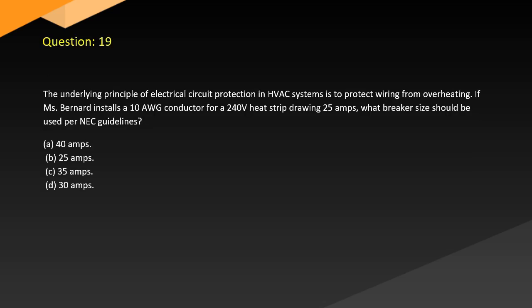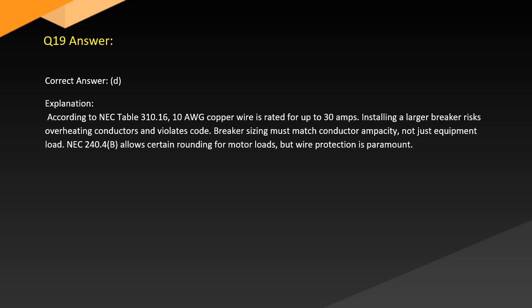Question 19. The underlying principle of electrical circuit protection in HVAC systems is to protect wiring from overheating. If Mr. Bernard installs a 10-gauge conductor for a 240 volt heat strip drawing 25 amps, what breaker size should be used per NEC guidelines? A. 40 amps. B. 25 amps. C. 35 amps. D. 30 amps. Answer. Correct answer. D. Explanation.